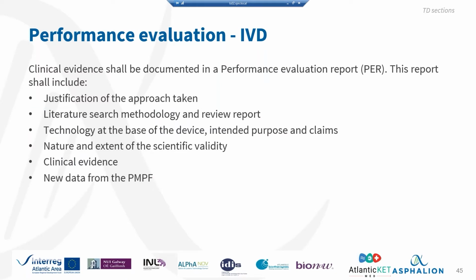It is an equivalent way to the clinical evaluation report for medical devices. And this report shall include a justification of the approach taken, the literature search methodology and review report. This is something we also did in medical devices. The technology at the base of the device, intended purpose and claims. This is also something we include in medical devices, like giving a bit of background of your device. You should also include the nature and extent of the scientific validity, the clinical evidence available to demonstrate compliance with the requirements, and then the new data from post-market performance follow-ups.